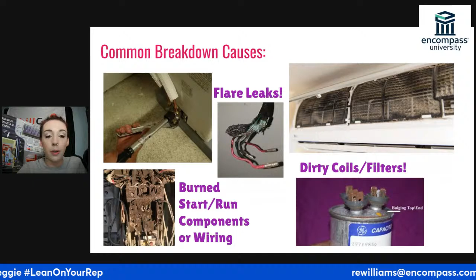What a lot of people do is put some Nylog on the face of the flare nut. We don't necessarily use it on the threads in this situation, because it's not a thread locker. All it will do is seal the flare, the flared bump, we call it, to the flare nut. So if you put a little bit of Nylog or another type of OEM lubricant on that and then squish them together, that's going to make your seal last longer. Now, if you put thread sealant or lubricant on the threads, it will make the nut spin on better and give you a better connection as well, but it won't actually seal anything. That's a common misconception for those of you who don't know.